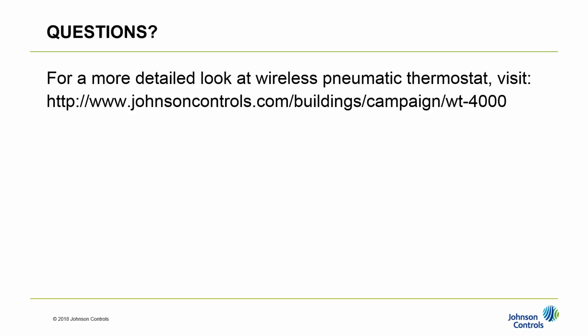So I'll throw this out to either of you. Will the stat communicate without the WT router repeater that Dan showed in his network diagram earlier? Yes, if it's a smaller network and it's close enough, it can talk directly to the WT BACnet IP. It does not require the routers, but on a typical installation, if you have quite a bit of space to cover and a larger number of stats, we do recommend them. The typical installation suggestion is for every 10 stats, you have one router. So that's the rule of thumb when installing.